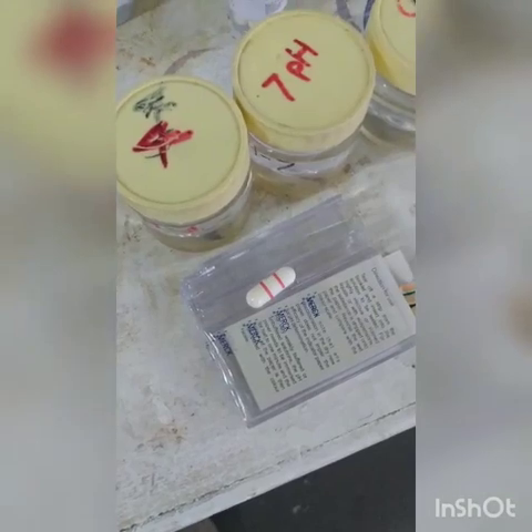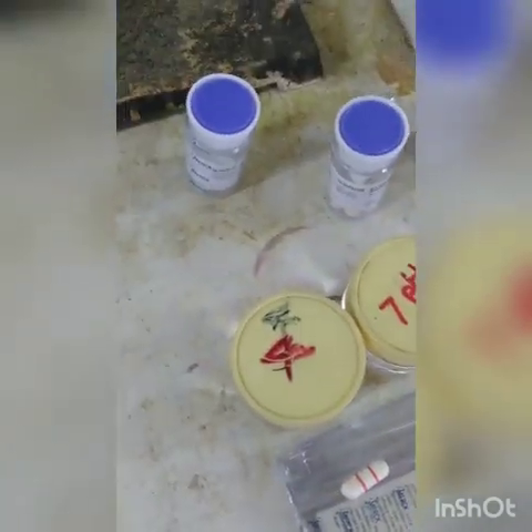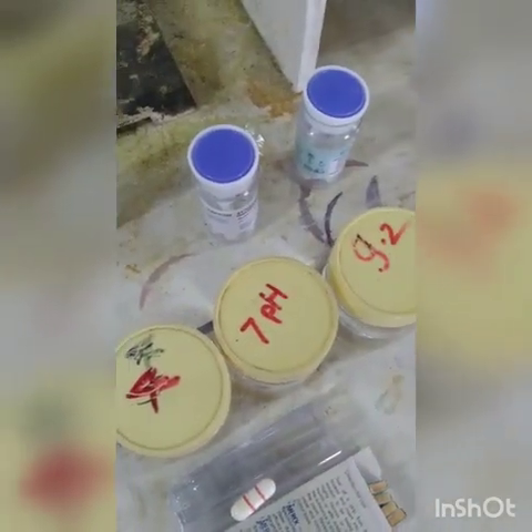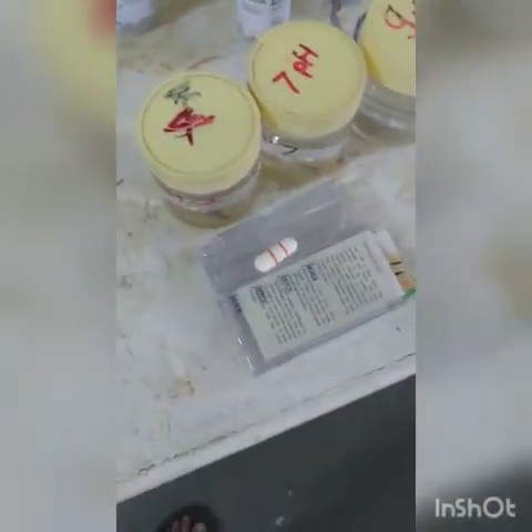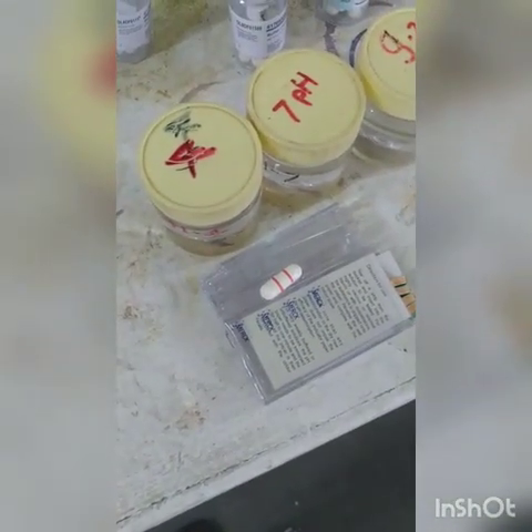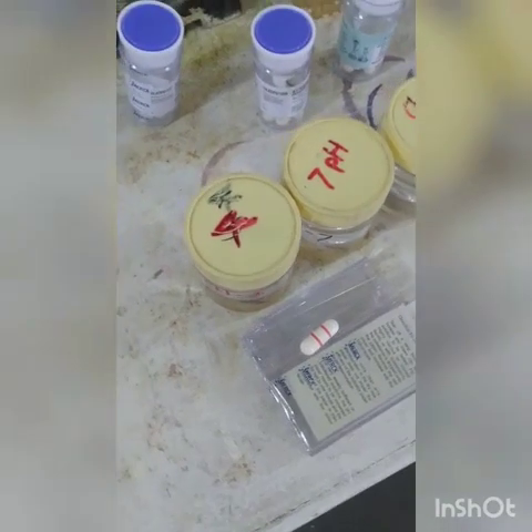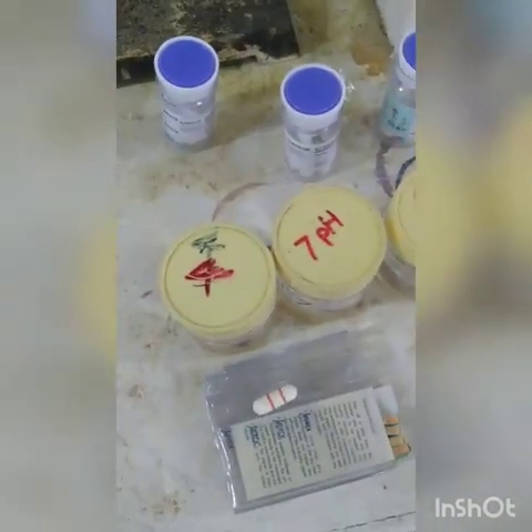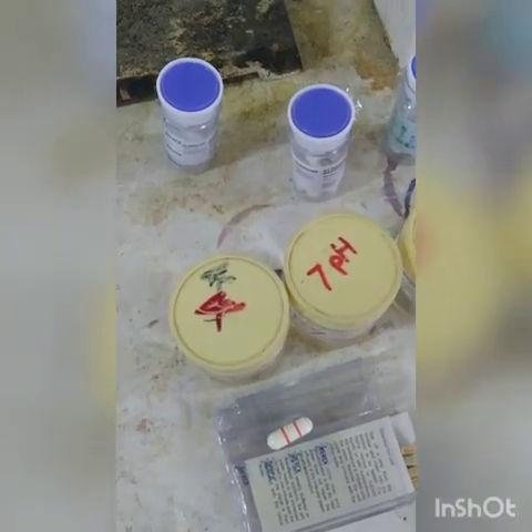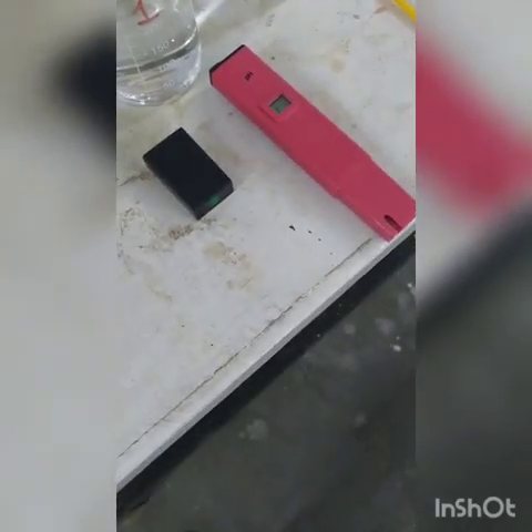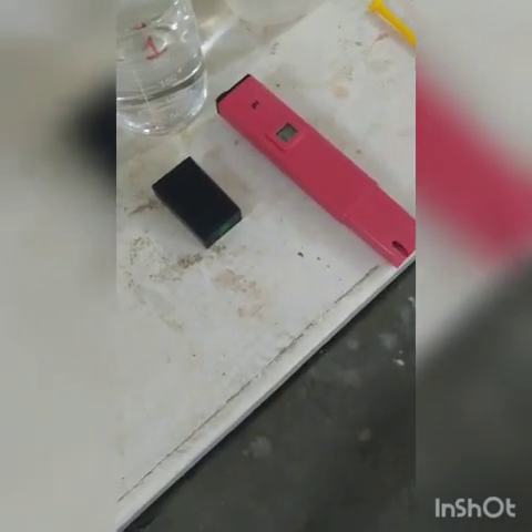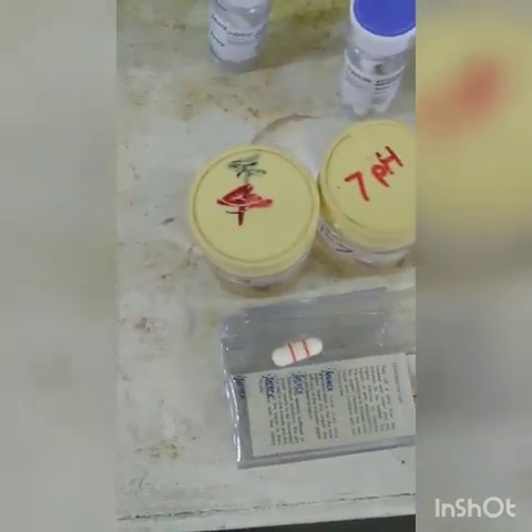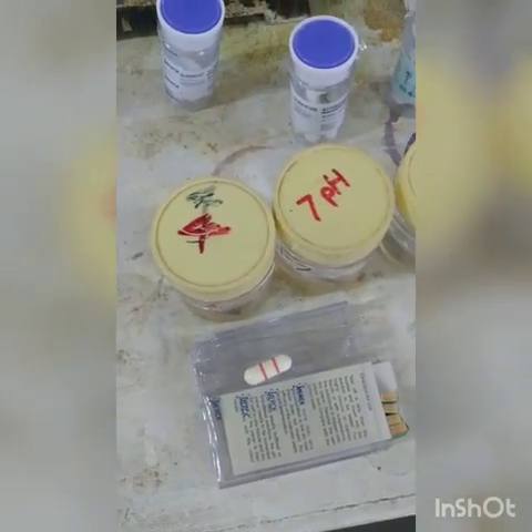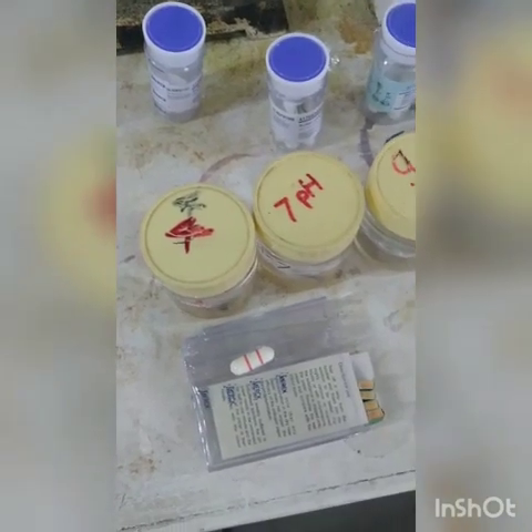These kinds of tablets are available for each of the pH values. As you can see, these are available in these bottles. So we have to put one tablet in 100 ml of distilled water. That will give us the corresponding value. So a pH 4 tablet is put and we get the value of 4, and similarly 7 and 9.2. By calibration, what we mean is we make this instrument read these particular values as pH 4, 7 and 9.2 respectively. As we know, pH is the negative logarithm to the base 10 of the concentration of H plus ion.